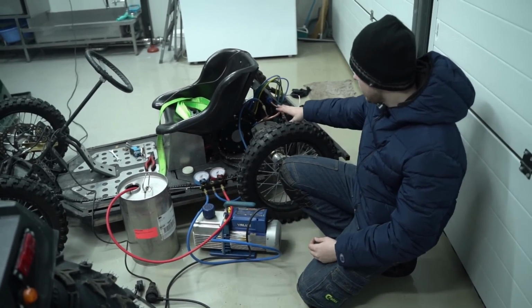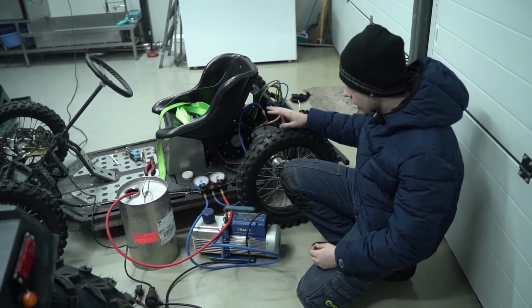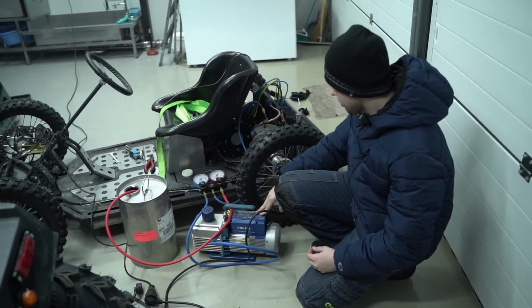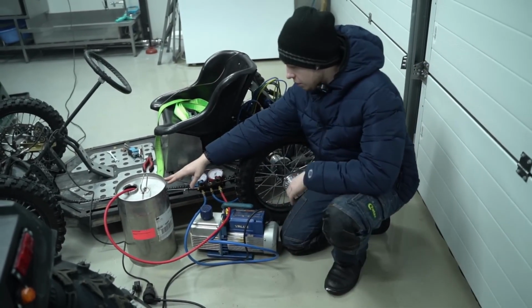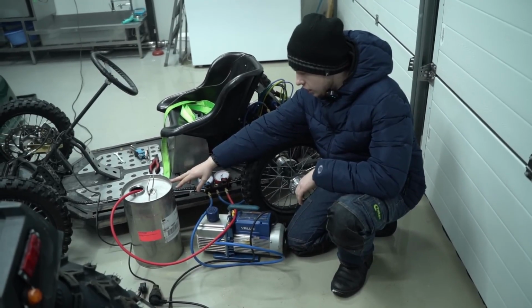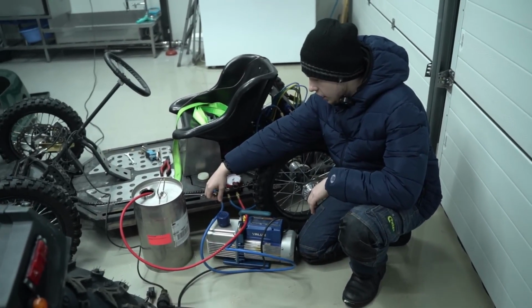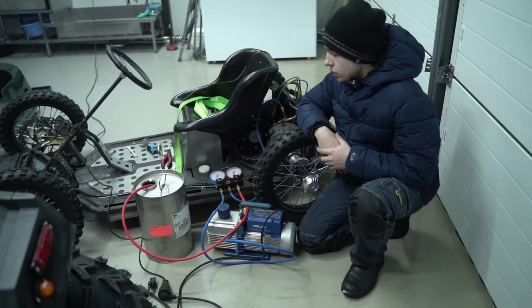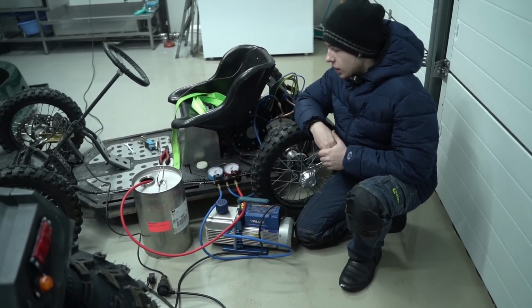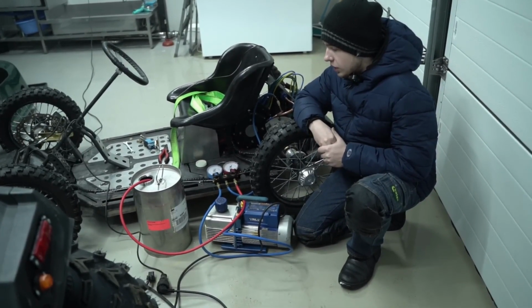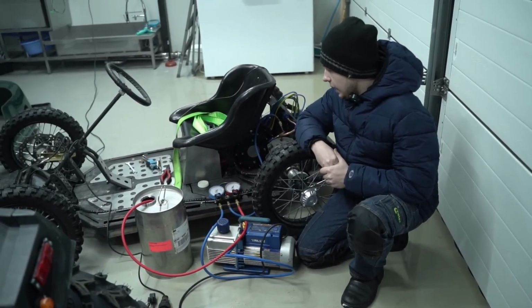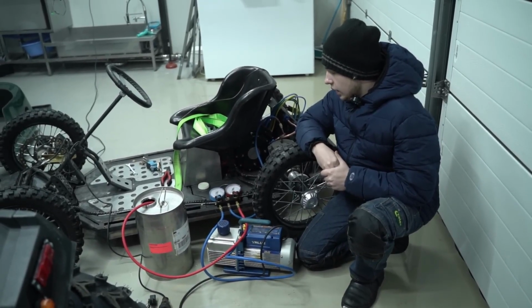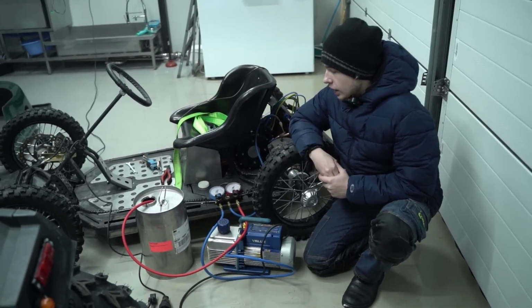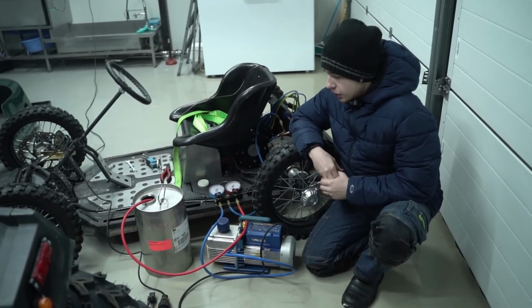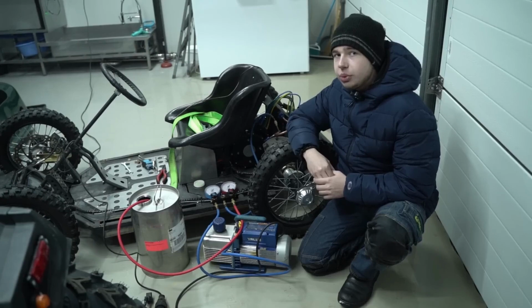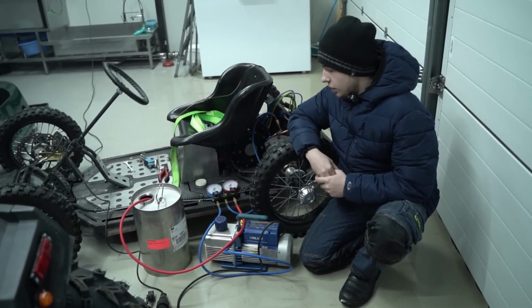And now actually the final stage. We're filling up our cooling system. First, we vacuum it out with a vacuum pump, and then we'll fill it with so-called dry water, specifically Novec 649. Its boiling point is around 49 degrees Celsius. The advantage is that, unlike R11 Freon, it doesn't corrode anything. Not rubber, not gaskets. But R11 does corrode things after all. It's also completely inert and acts as a dielectric. Basically, it's used for extinguishing electronics fires. Its boiling point, of course, is a bit higher, 49 degrees.